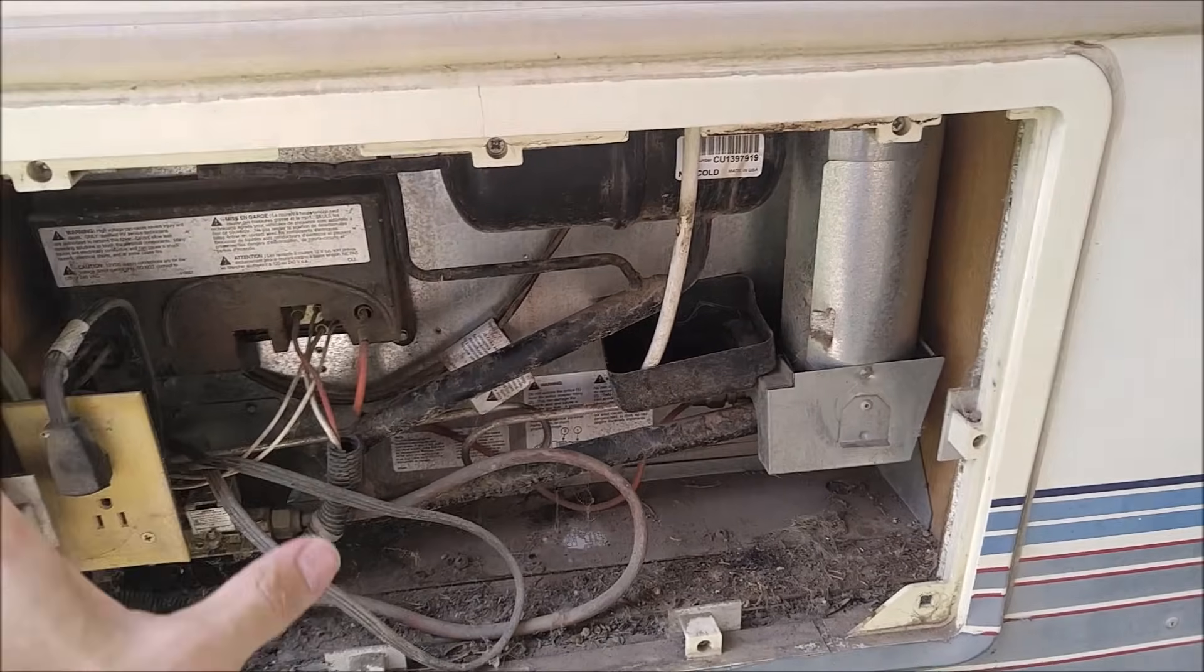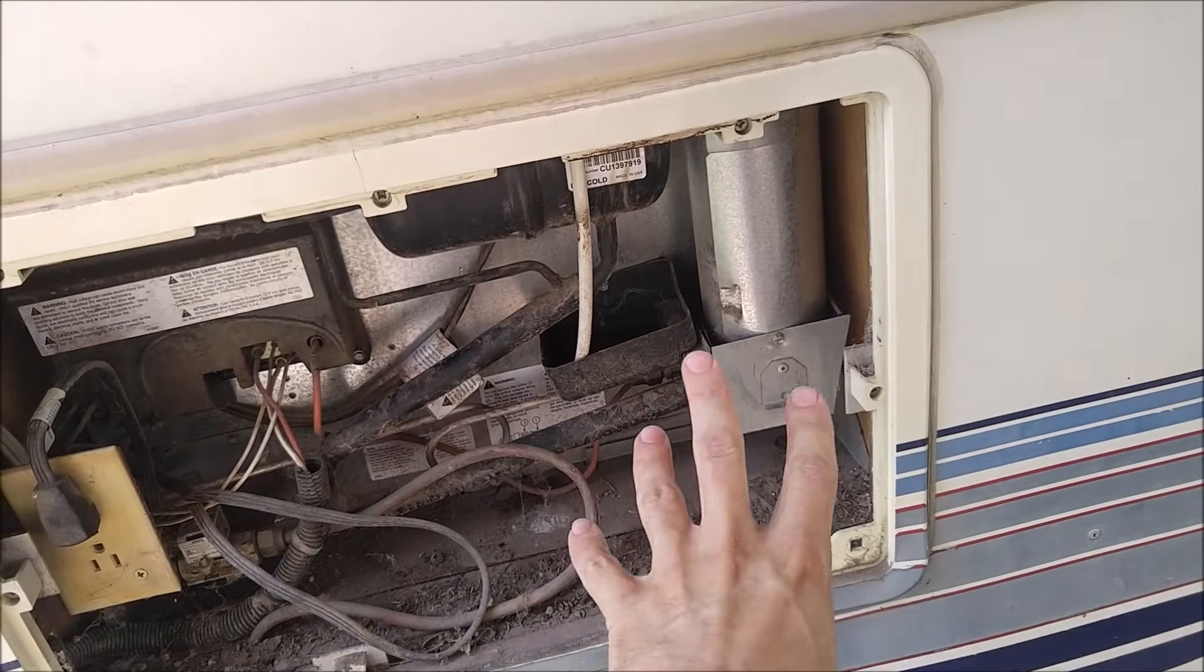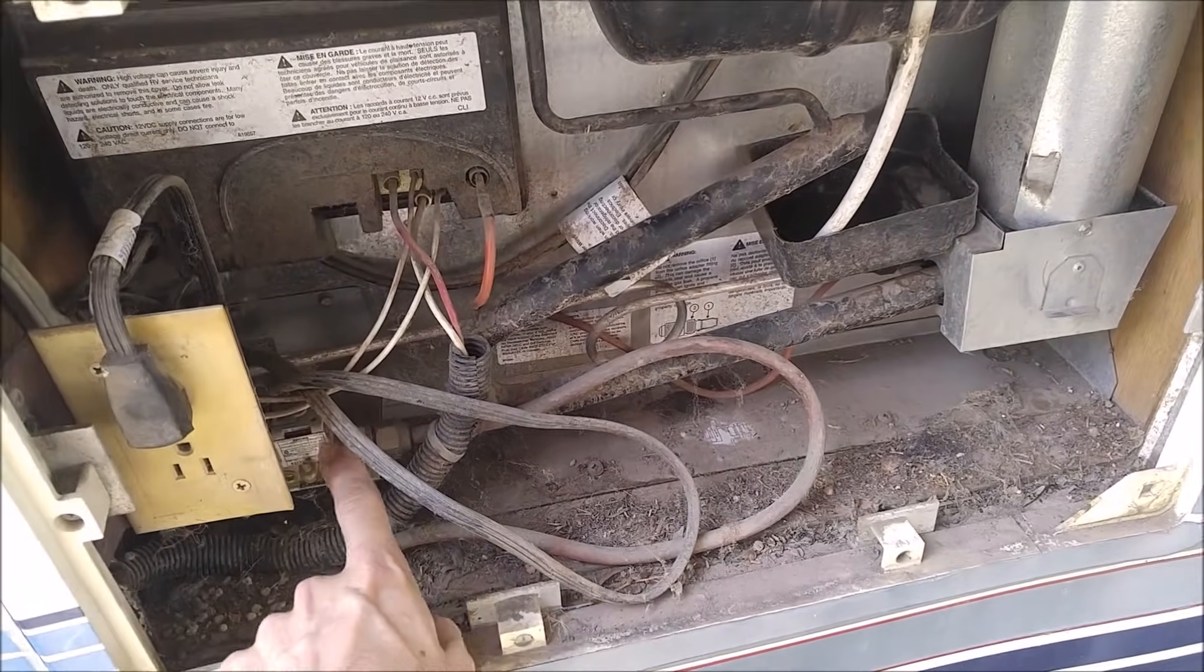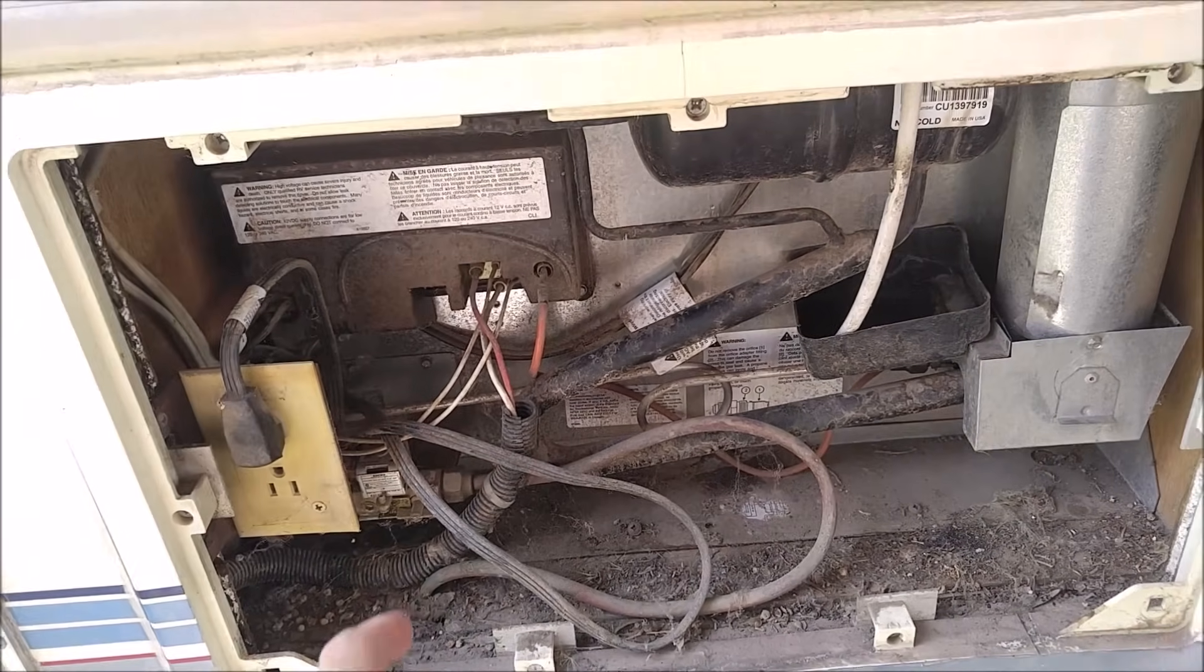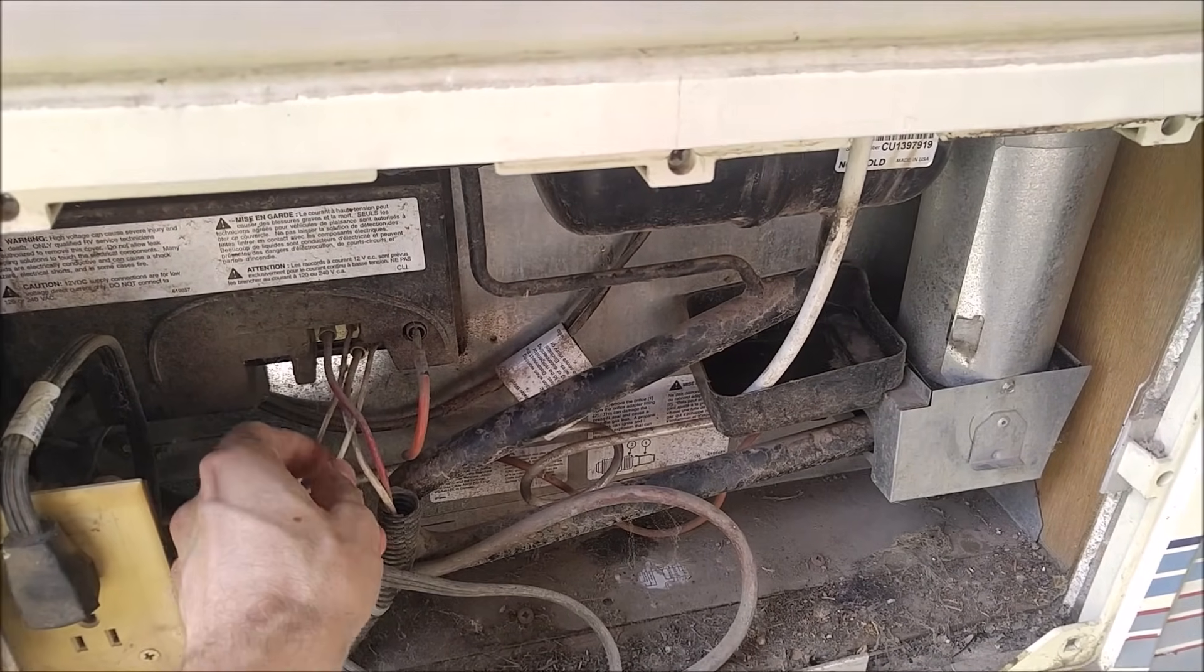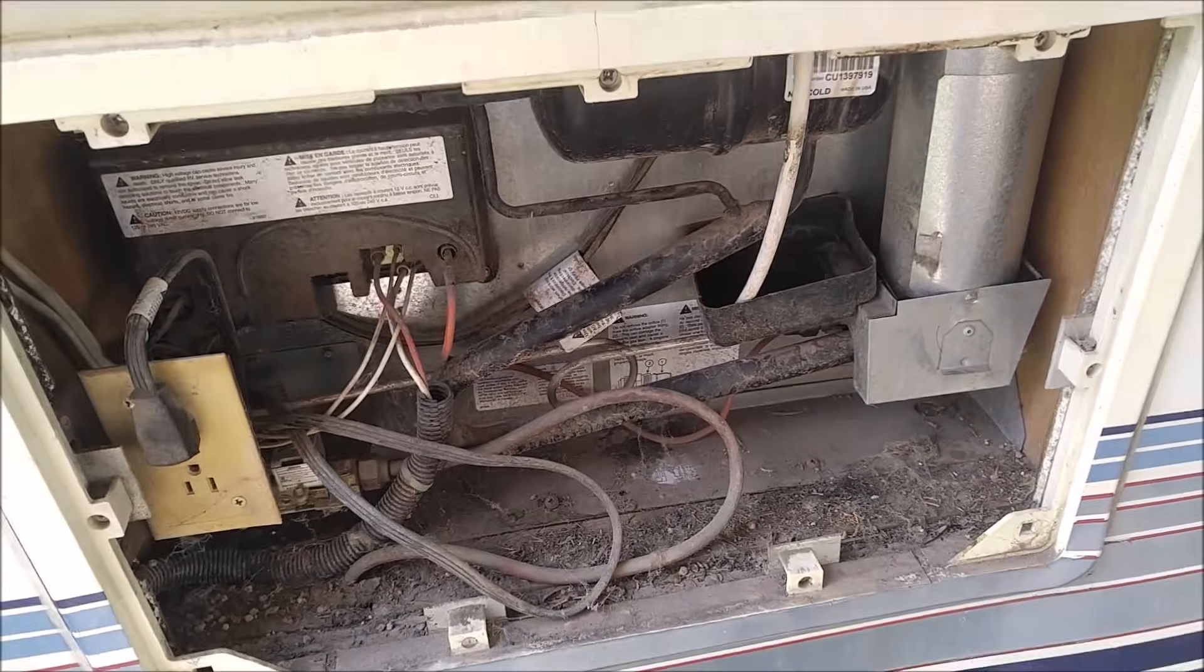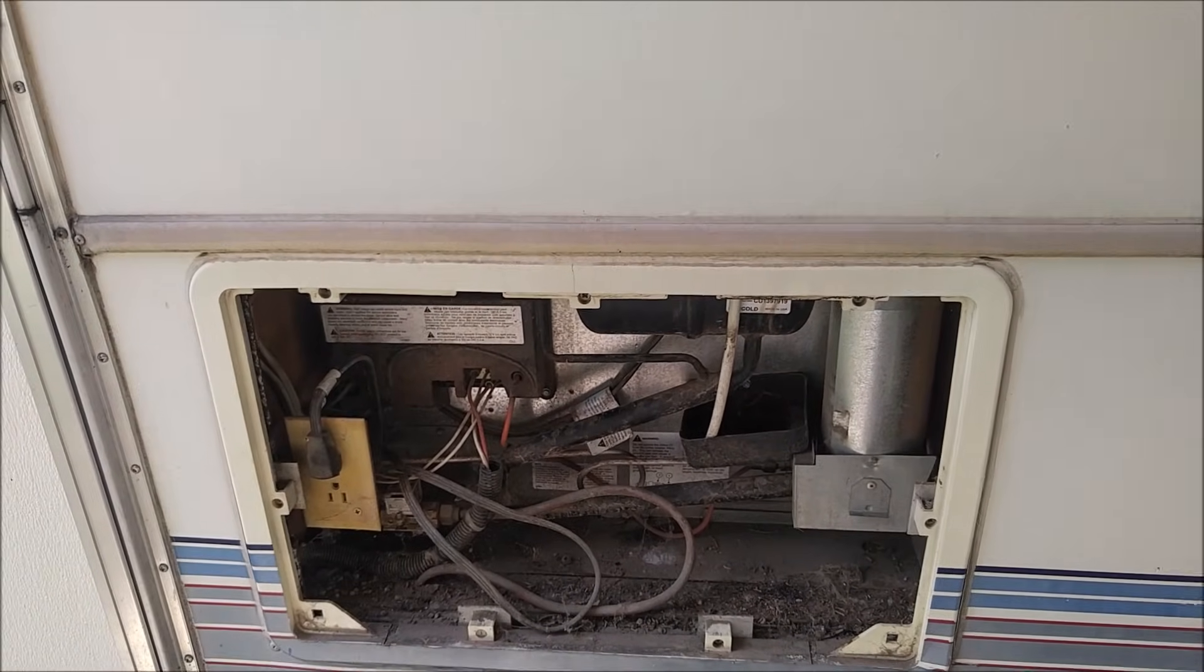You know, the AC problems can be fixed either wiring or control board. The gas problems can be fixed via either cleaning the flue, checking the solenoids. Sometimes the solenoids get clogged up with stuff from the gas line. I've had that happen before. You can actually take those apart and clean them, or it might just be a control board issue as well and it's not getting 12 volts to turn the solenoid on. Very simple. Very easy. Make sure you hit the thumbs up button on the video and subscribe to the YouTube channel.